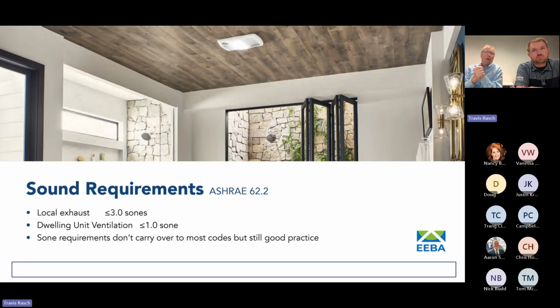A little bit of a side note, one of the requirements in ASHRAE is also regarding sound. They say for local exhaust, that bath fan or kitchen range should be a maximum of 3 sones. And for dwelling unit ventilation, if you're going to use a bath fan that's running 24 hours a day, that should be less than 1 sone. The reason they're concerned about this, obviously, is if people find the noise objectionable, they're going to turn off the device and then you have no airflow at all. But as I note in the last bullet here, these requirements do not carry over into the I codes. So there's nothing in the IRC or IMC regarding sone limitations, but obviously it's still a good practice. As builders out there in the audience, firsthand, you don't want callbacks, and that's a very simple callback to avoid.